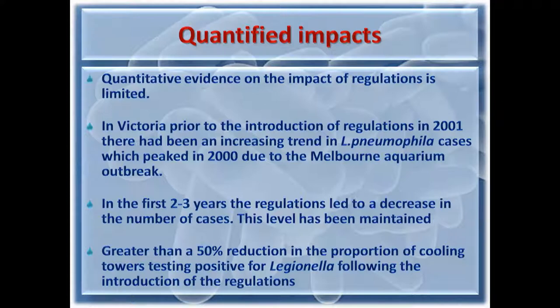In Victoria, which was the first state to introduce regulations, they had shown that before the regulations in 2001, there had been an increasing trend in Legionella pneumophila cases, and that peaked in 2000 due to the Melbourne aquarium outbreak. In the first 2 to 3 years, the regulations produced a decrease in the number of cases. This level has since been maintained or plateaued. We haven't seen much reduction in recent years. They also showed greater than a 50% reduction in the proportion of cooling towers testing positive for Legionella following the introduction of regulations.